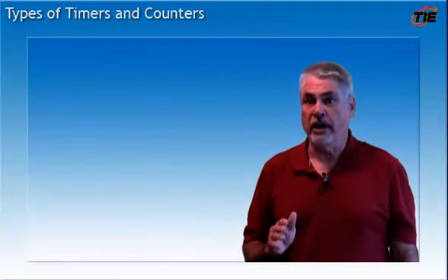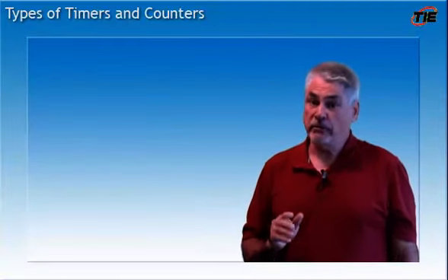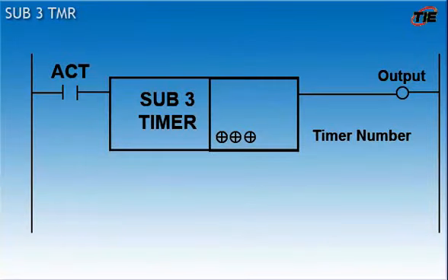Each of these timer function statements uses a contact known as an action command, or ACT, to start the operation. Basically, this gets the timer to start timing. The actual time value can deviate depending upon the scan time of the ladder. Timers in level 1 of a ladder will be more accurate. Level 2 timers may deviate due to the scan sequence. Like many function statements, there are settings that determine how it will be used. Let's start with the sub-3 timer and see how it works.